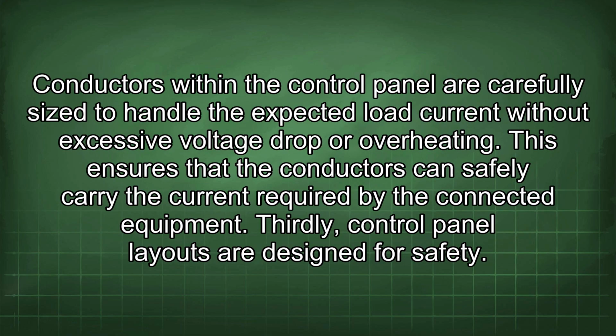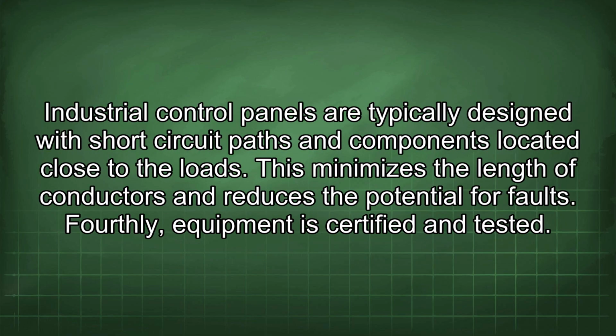Conductors within the control panel are carefully sized to handle the expected load current without excessive voltage drop or overheating. This ensures that the conductors can safely carry the current required by the connected equipment. Thirdly, control panel layouts are designed for safety. Industrial control panels are typically designed with short-circuit protection components located close to the loads. This minimizes the length of conductors and reduces the potential for faults.